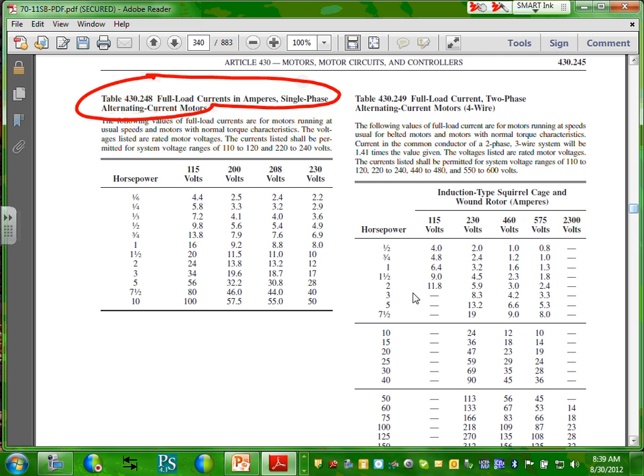Okay, so everybody knows how to use this table. The most common mistake is how to use it. We use these tables if your voltage is between 110 to 120, 220 to 240. Any voltage in between, very important for single phase system. Okay, so what's the voltage of my system? The voltage of my system is 240.